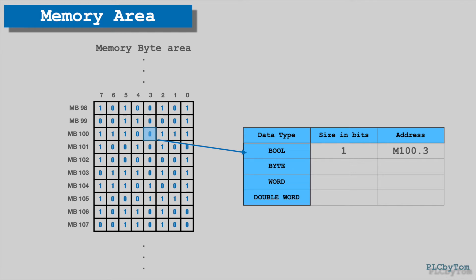Letter M represents that it accesses the memory area. To address data one byte length, address format will be MB102, where M represent memory area, B represent that data is one byte long and 102 represent byte number.